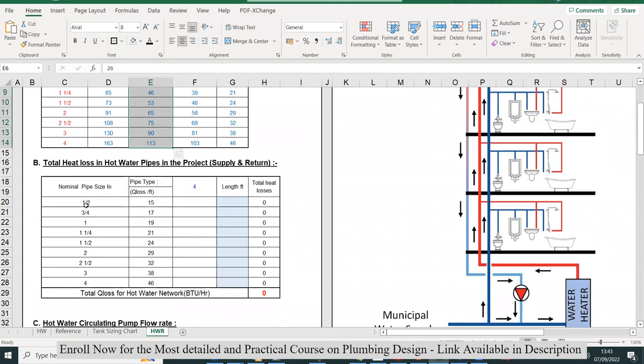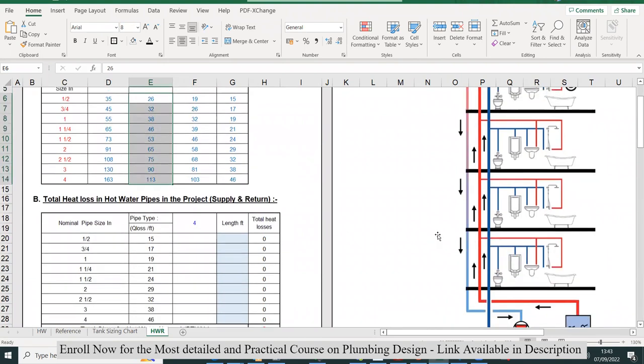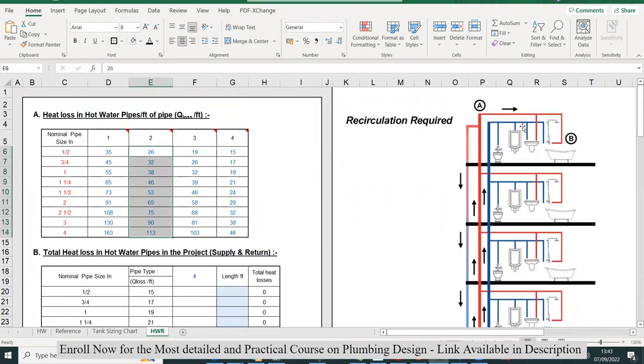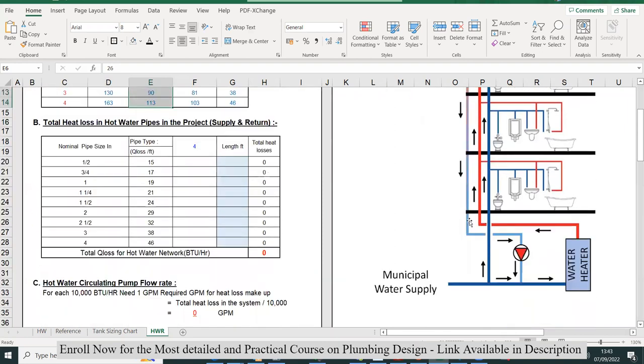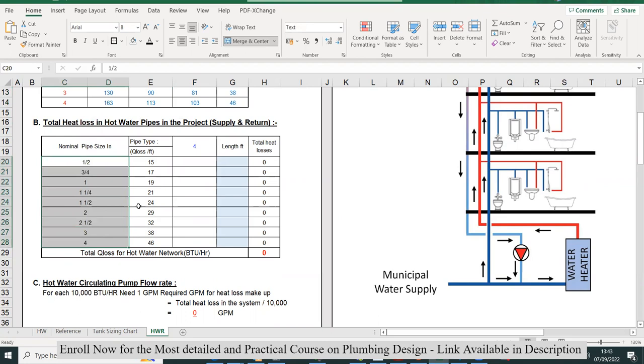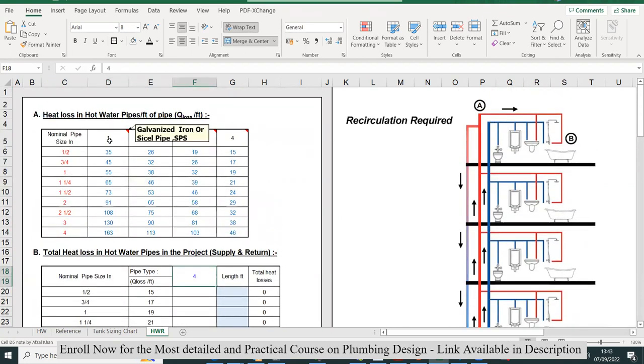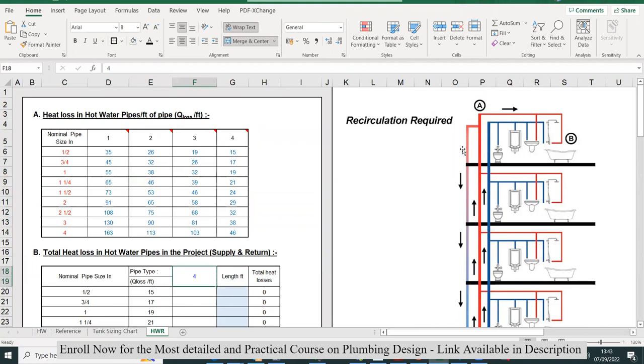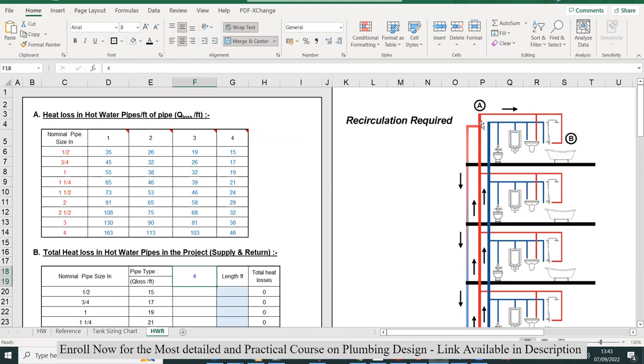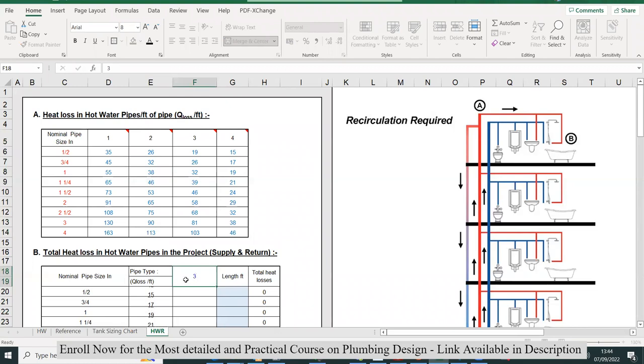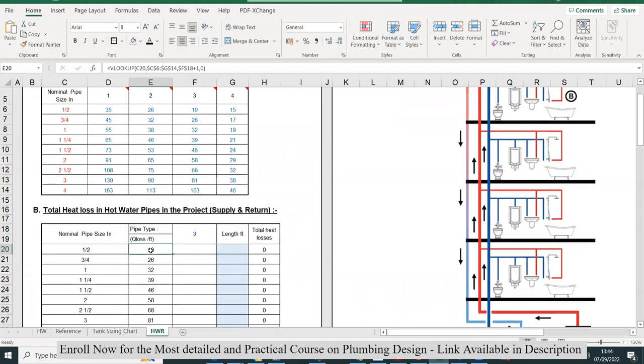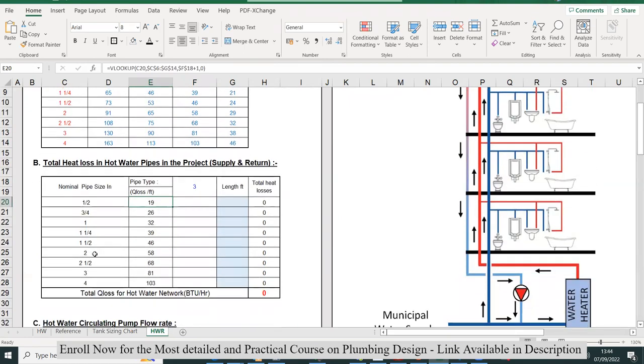Next, you have to calculate the total piping length of the hot water supply plus hot water return. These are the pipe sizes that you have, and you write the number here. For example, one, two, three, four. In this project I've used copper tube for hot water supply and return. Copper tube refers to number three. When you write three here, it will take all those heat loss values for these pipe sizes.